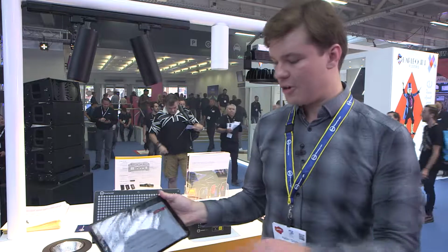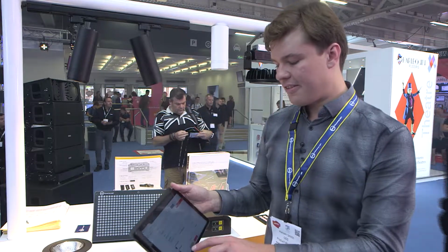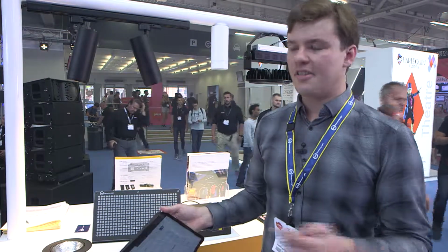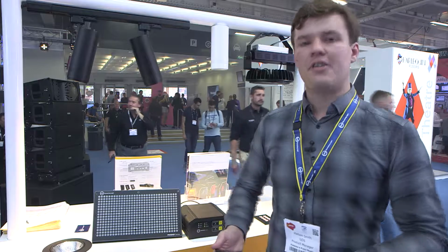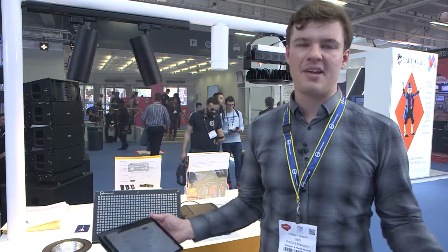Going into the settings for an outstation, as well as the various controls for setting the scenes that are assigned to the outstation, there's also an external switch input, and you can use that to connect something like a fire alarm system or a paging system that could trigger an emergency scene from the Prodigy. Or you could even set a switch that would lock down the outstation to stop it from being tampered with.